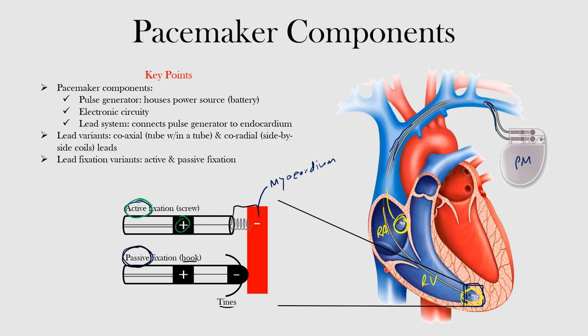Disruption of the conductor elements can result in high impedance, such as from a fracture, while disruption of insulation materials can result in low impedance due to short circuiting, such as from an insulation breach.